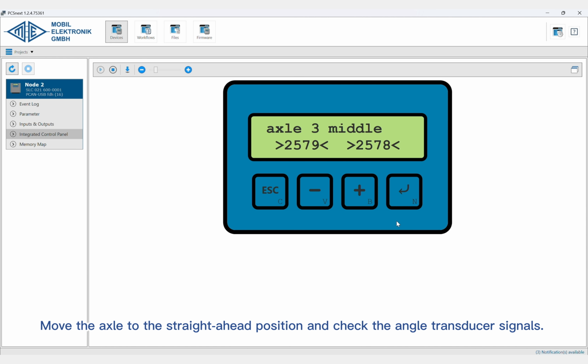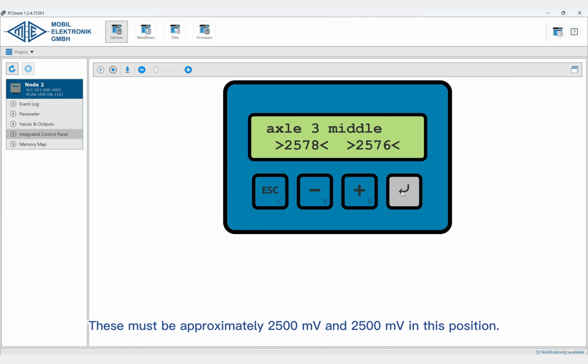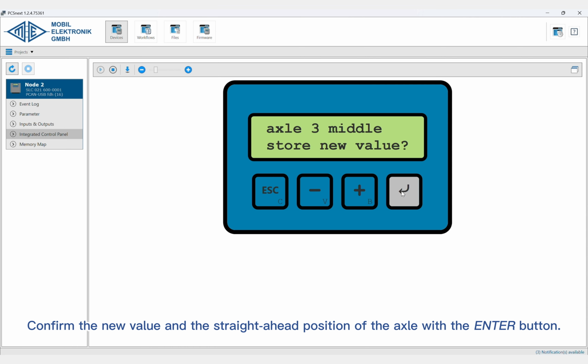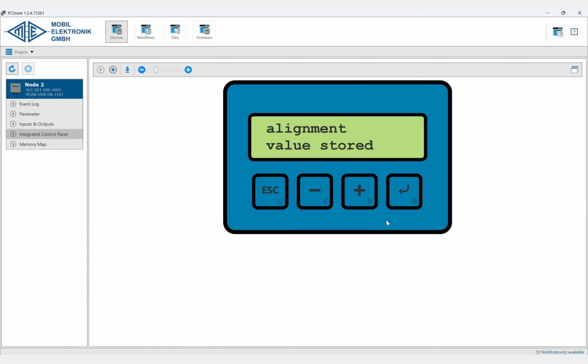Move the axle to the straight-ahead position and check the angle transducer signals. These must be approximately 2,500 millivolts and 2,500 millivolts in this position. Confirm the new value and the straight-ahead position of the axle with the Enter button.